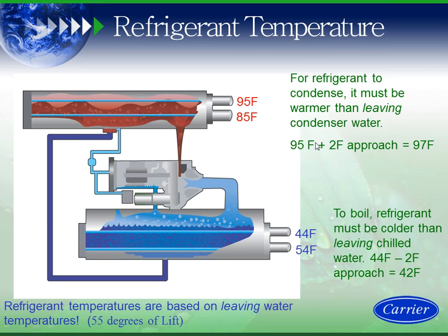So therefore I would be 95 plus a 2-degree approach, which is a 97-degree saturated condensing temperature. The saturated suction and saturated condensing temperatures are a determinant of the chiller efficiency itself. In this case, we have 55 degrees of lift, but this is based on design temperatures, right? This is that 1% of a year, if it ever happens on a chiller plant, where my building is fully occupied, it's a design day outside, and I'm producing these types of situations.